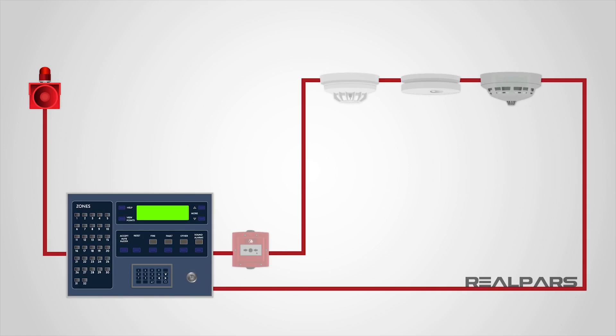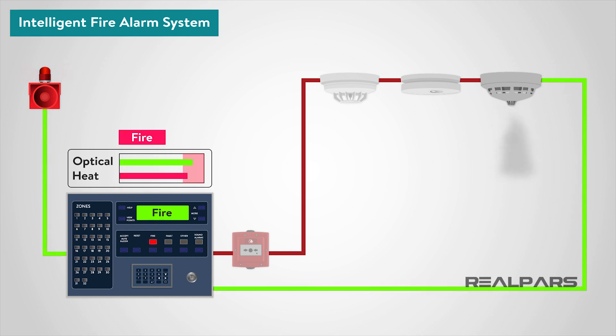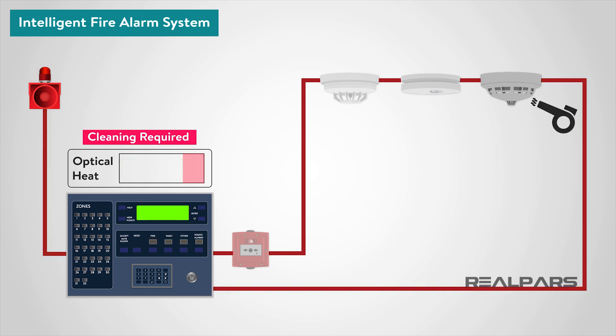However, in our next type of system, which is an intelligent fire alarm system, each detector effectively incorporates its own computer, which evaluates the environment around it, and communicates to the control panel whether there is a fire, fault, or the detector head needs cleaning.